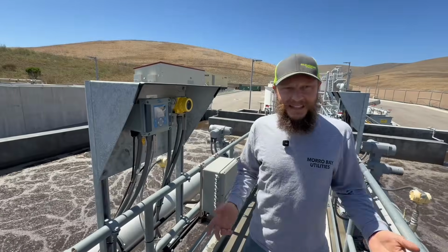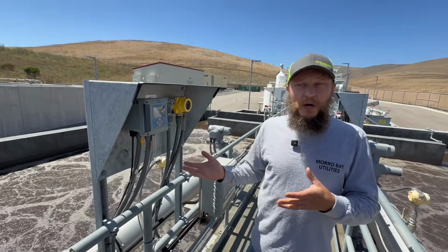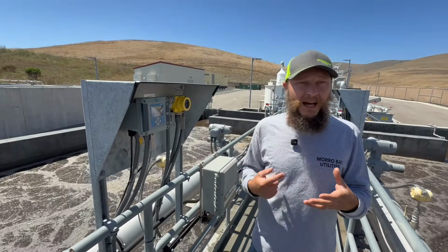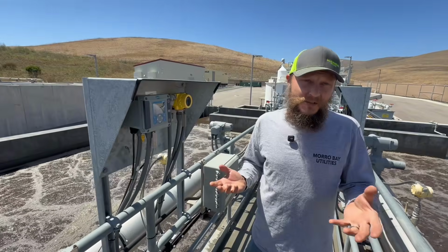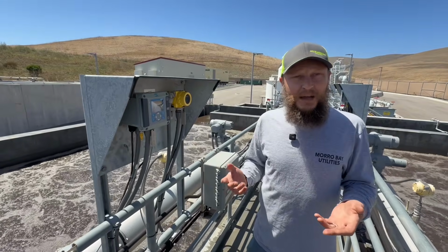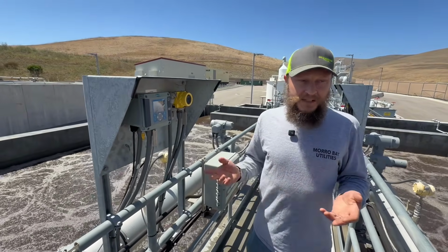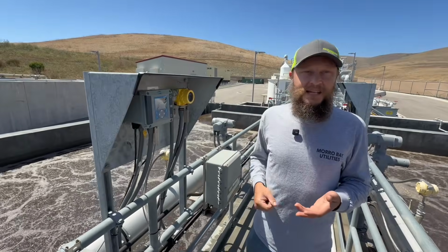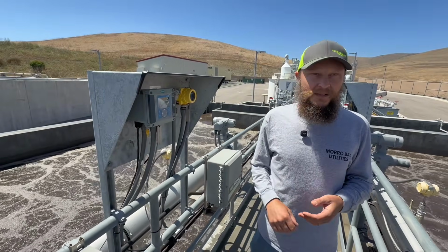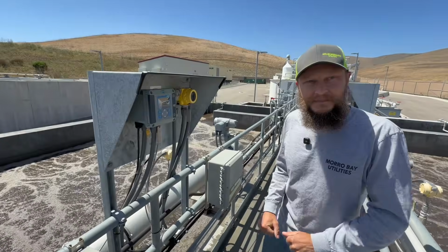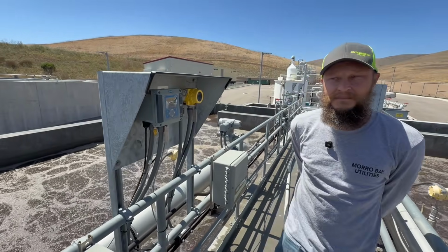So they don't fall in, right? Yeah. Well, this is so you know if there's power flowing through that line. If it's 0 milliamps and that's your 0, then you don't really know if that wire is hooked up or not. But now if you see a 0, it's a telltale sign that you've got a broken conductor, not connected.